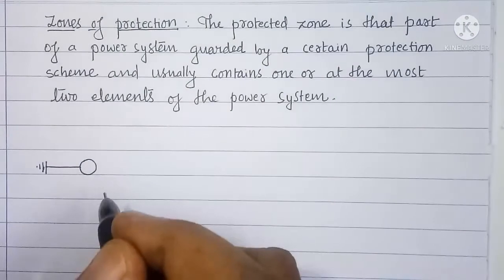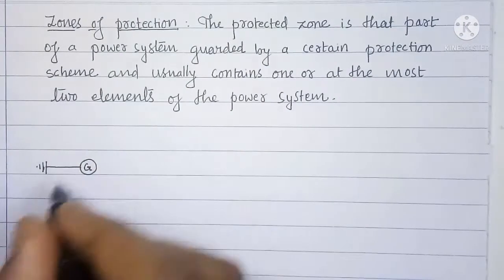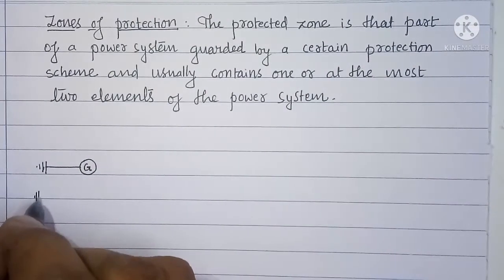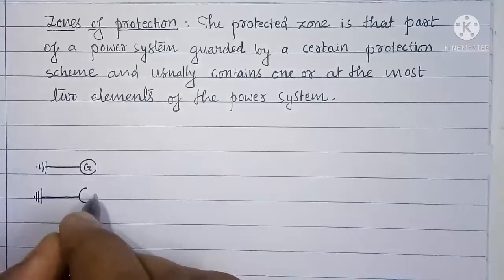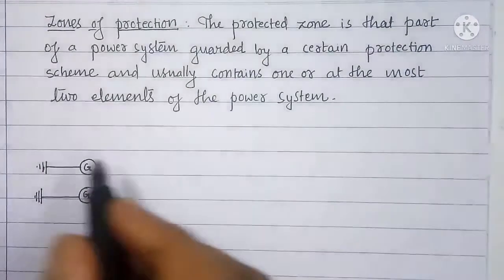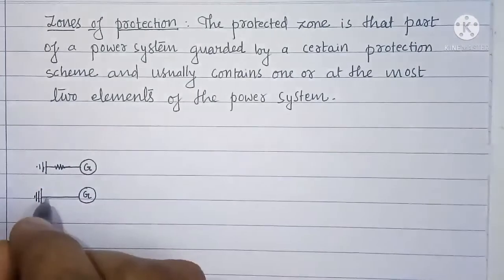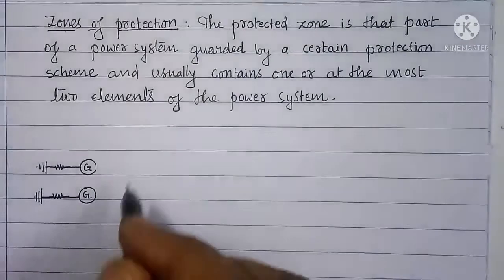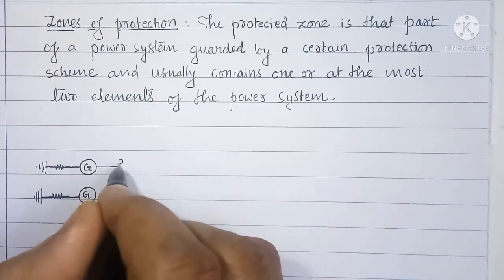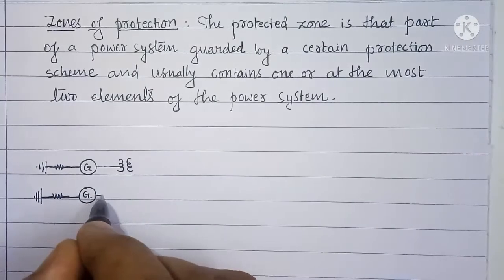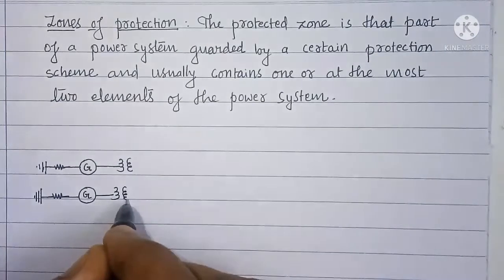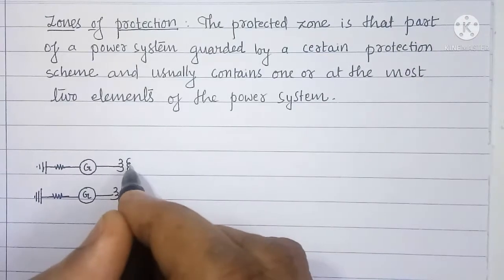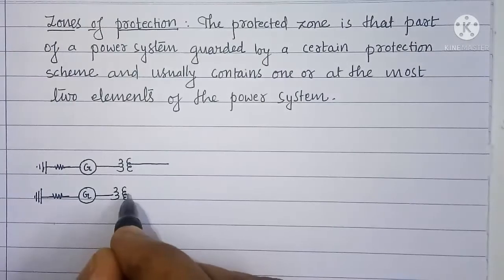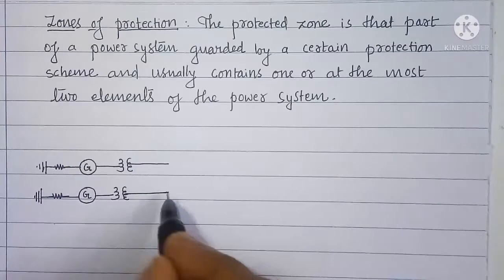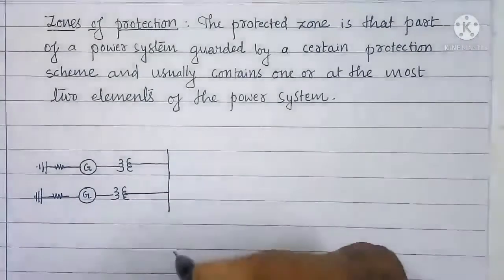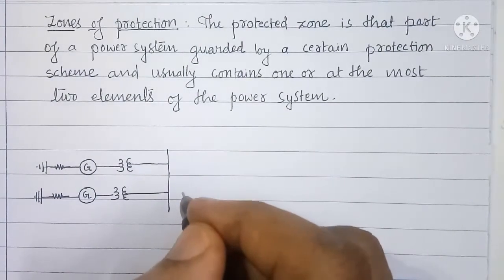I will consider one power system having two generators. First generator, the second generator. Resistive grounding is used for both the generators. And here are the generating station transformers, which are usually step-up transformers. And the two generators operate in parallel and feed their power to a common bus. Bus is nothing but a thick conductor which operates at constant voltage.